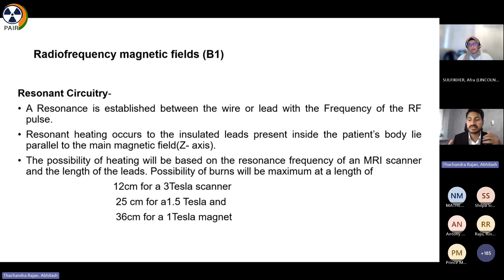And if it is in the Z-axis, I mean the head to feet direction of the patient, and if it is in this particular length, for a 3 Tesla scanner, it's 12 centimeter. For a 1.5 Tesla scanner, it's 25 centimeter, and for a 1 Tesla scanner, it will be 36 centimeter. This is calculated as per the resonance frequency of the particular scanner. For 3 Tesla, it's 128 MHz, and half of the wavelength will be approximately 12 centimeter. And this is calculated accordingly. So when we move from a 3 Tesla scanner to a 7 Tesla scanner, what will happen? This 12 centimeter will come down to 5 or 6 centimeters. Most of our implants are within that range. So there will be a drastic increase of RF related, especially the resonance circuitry burns, when we move from 3 Tesla to a high strength like a 7 Tesla magnet.